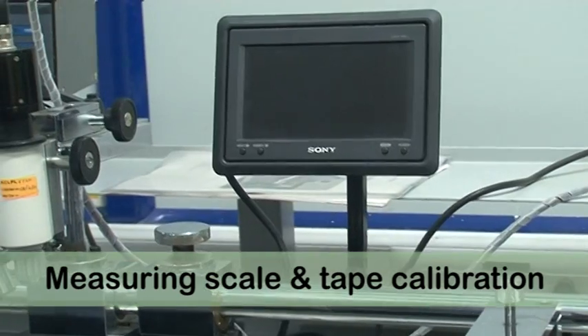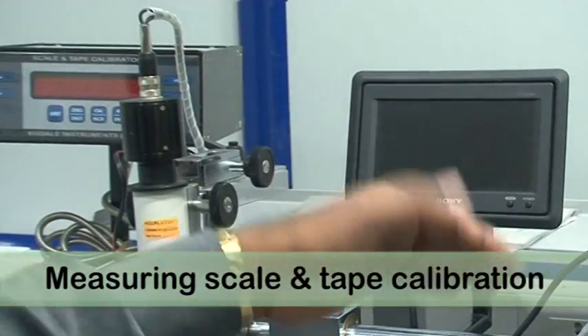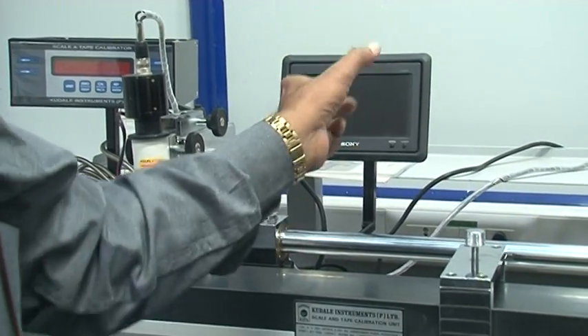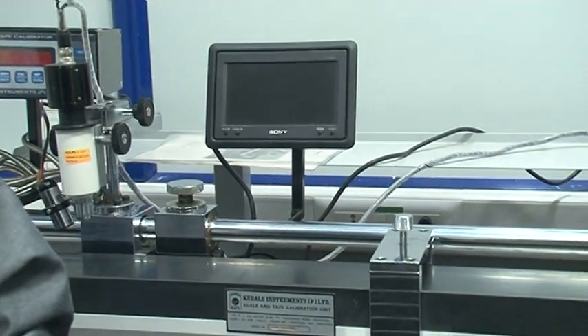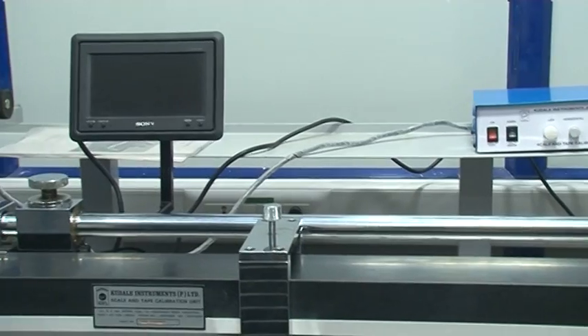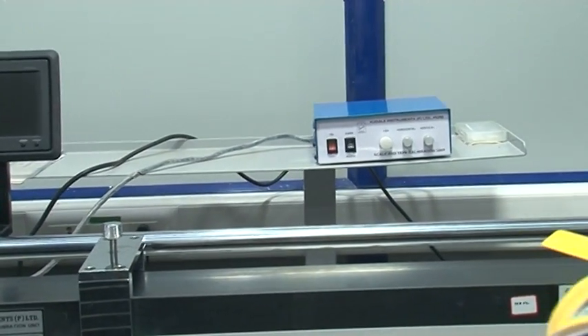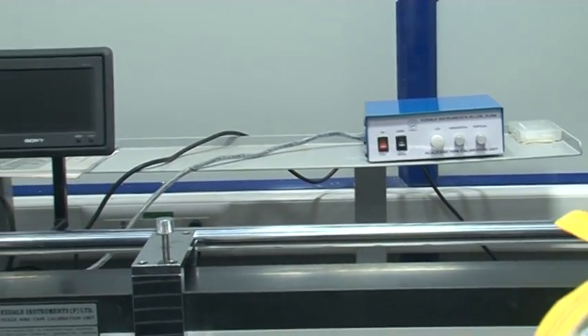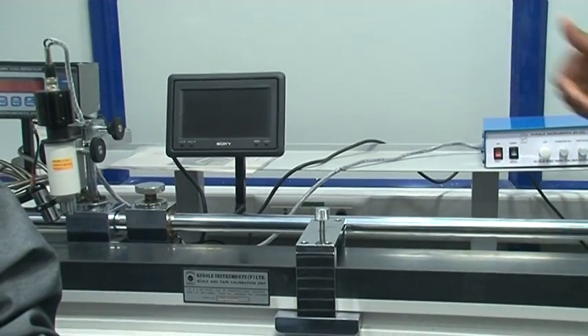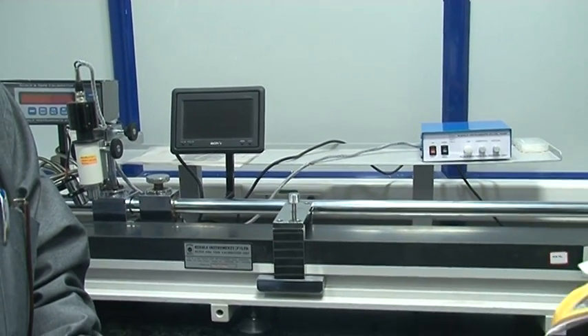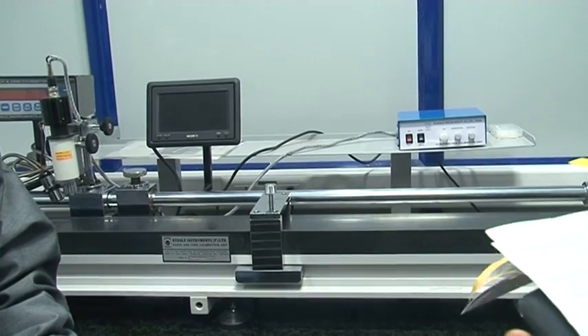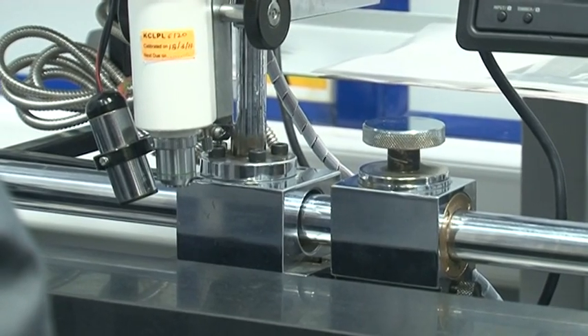Tape and scale calibration unit. On this unit we can calibrate measuring scales as well as measuring tapes. The range of this unit is 1000 mm and the least count is 5 micron. With the help of the DRO and camera we can measure graduations on a scale or tape with magnification. In case of a tape, readings are taken in steps of 1000 mm.